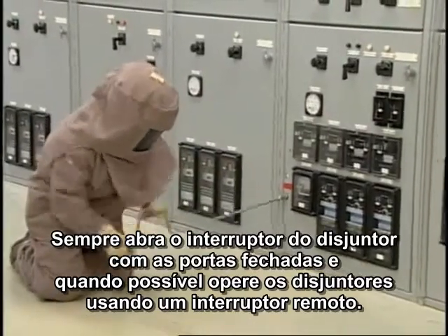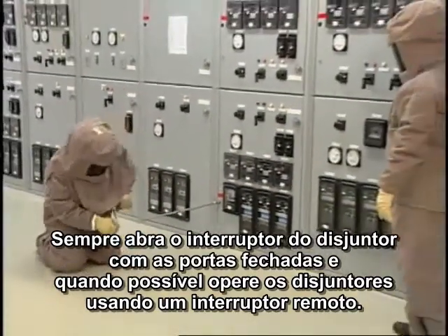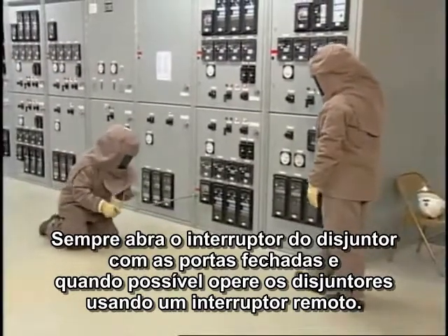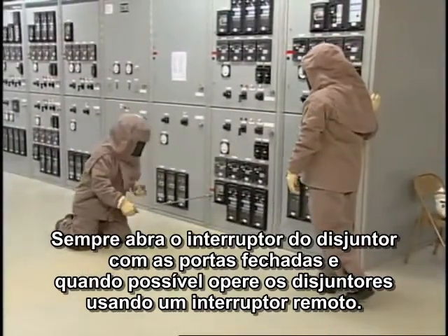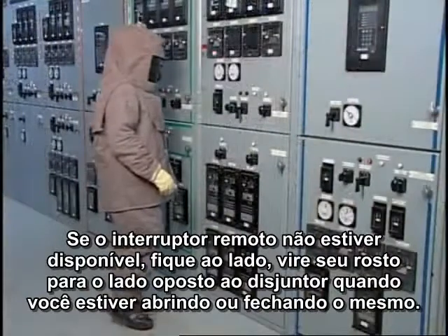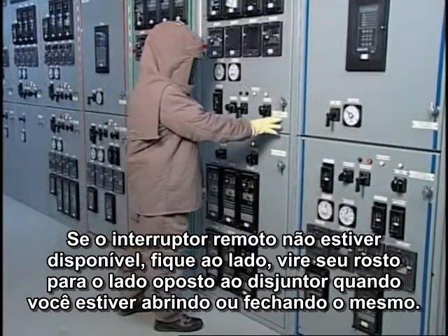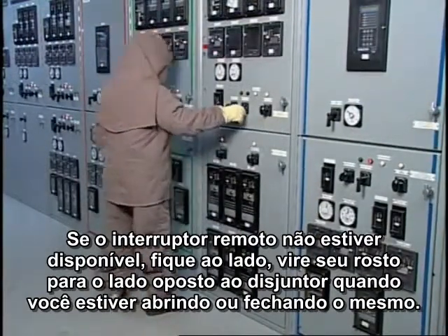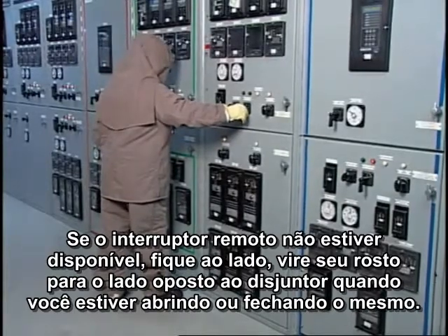Always open rack in and rack out circuit breaker switches with doors closed. Whenever possible, operate breakers from remote control switches. If remote control switches are not available, stand to one side and turn your face away from the breaker when opening or closing the breaker.